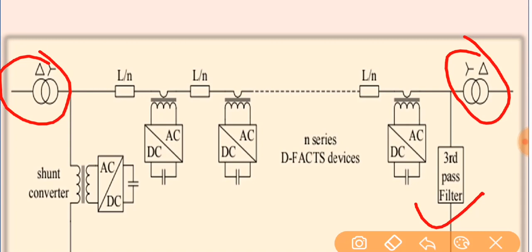The series converter consists of multiple units that are connected in series with the transmission line. These series converters inject a voltage where the phase angle is controllable over 360 degrees and where the magnitude is controllable as well. These series converters also control the power flow through the line, and the function of the shunt converter is to compensate reactive power to the grid and to supply the active power required by the series converters. There is no common link between these series and shunt converters in the DPFC. So the active power is exchanged by the harmonic through the AC network, and this is the construction of the DPFC.